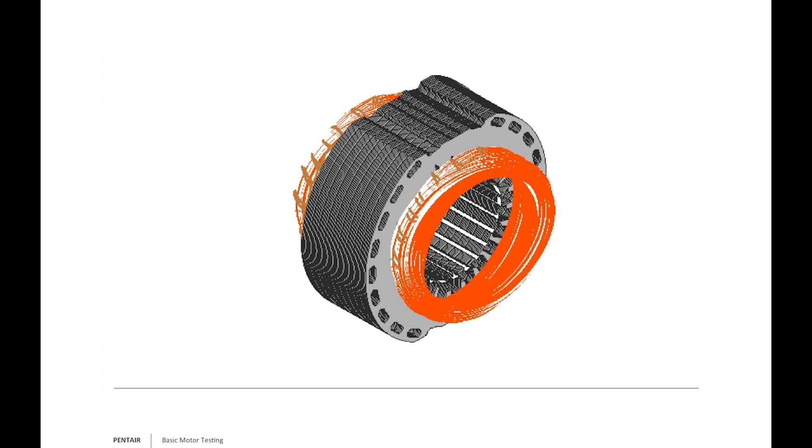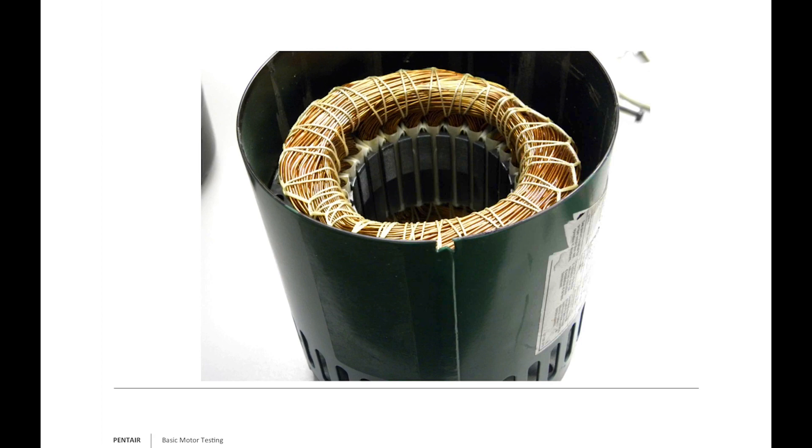When we're testing, we're looking at those wires — think of them as one continuous piece. Brand new windings are beautiful: lacquer covers the copper, they're shiny, strings are attached, and mylar protects the stator from the windings. Old timers say all motors run on smoke — the minute you let the smoke out, the motor's dead. Something catastrophic happens, the windings become like toaster elements, overheat, and flash-burn the lacquer and strings off in a poof of smoke.